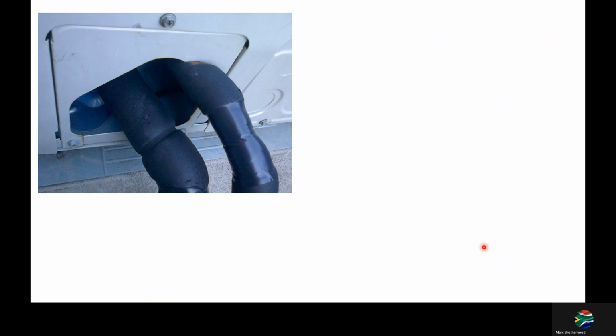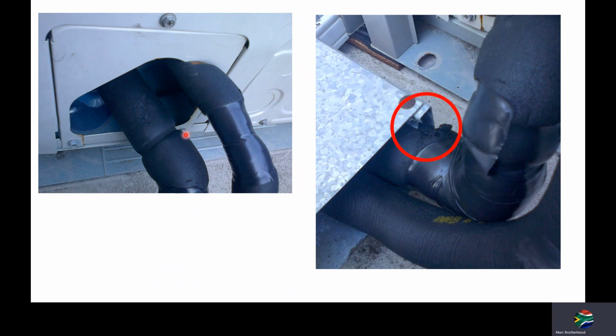Let's look at some other outdoor errors or poor installation practices. This is pipework related. You can see here how within a very, very short period of time the frame of the unit is going to cut right through the pipework and create a big refrigerant leak. Here in these support trays, the installer didn't consider these sharp edges. These are much harder metal than copper, and it's just going to cut right in and create a fracture, and you're going to lose all your refrigerant.